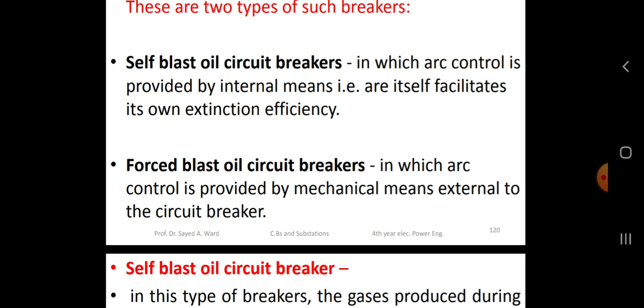In this type of circuit breaker, the gas produced during arcing is confined to a small volume by using an insulating rigid pressure chamber or explosion pot surrounding the contact. The space available for the arc gases is restricted by the chamber, so a very high pressure is developed to force the oil and gas through the arc and extinguish it. The magnitude of the pressure depends upon the value of the fault current to be interrupted. The arc itself generates the pressure, so such breakers are also called self-generated pressure oil circuit breakers.